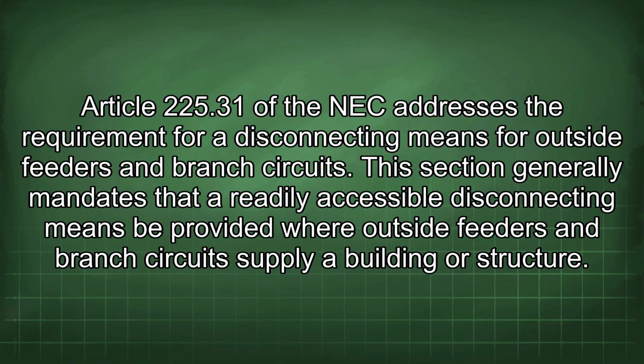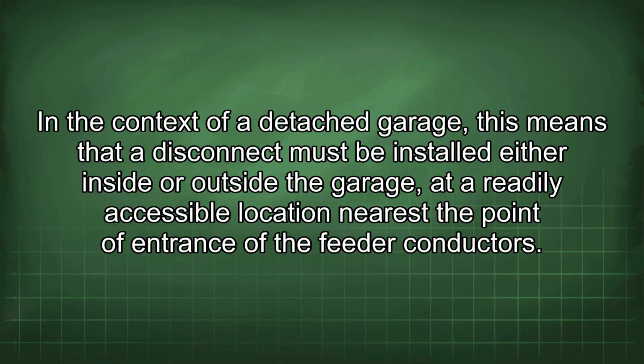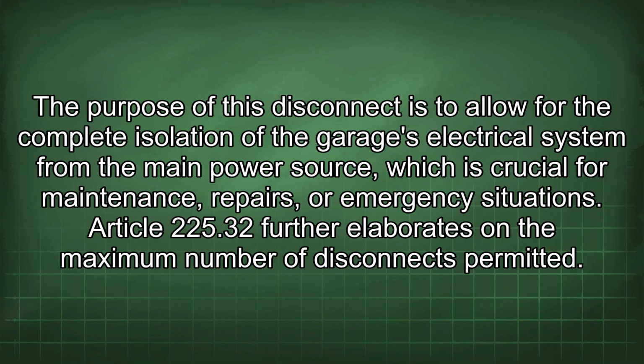Article 225.31 of the NEC addresses the requirement for disconnecting means for outside feeders and branch circuits. This section generally mandates that a readily accessible disconnecting means be provided where outside feeders and branch circuits supply a building or structure. In the context of a detached garage, this means that a disconnect must be installed either inside or outside the garage at a readily accessible location nearest the point of entrance of the feeder conductors. The purpose of this disconnect is to allow for the complete isolation of the garage electrical system from the main power source, which is crucial for maintenance, repairs, or emergency situations.